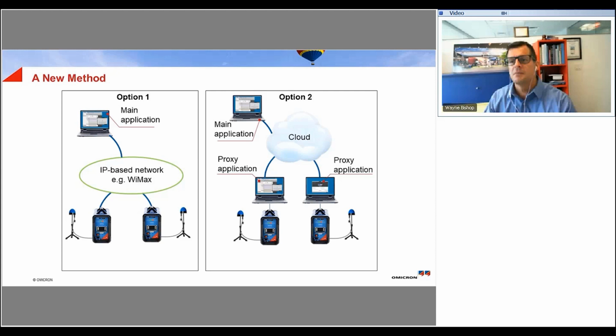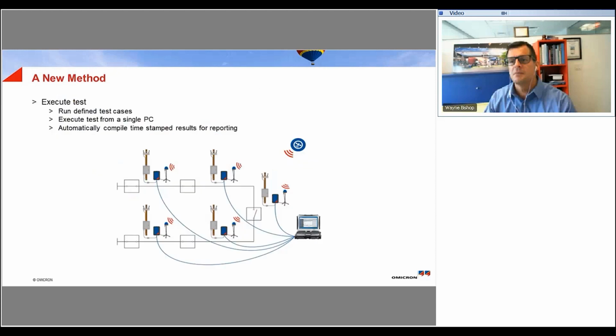So once we establish some kind of synchronization, whether it be GPS, IRIG-B, whatever it is, the test cases can then be executed. The software can then calculate the resulting fault values for each device at each location. If this test is now executed, the testing software should be able to upload all the test values into all of the test sets simultaneously via the GPS synchronization at the remote end. And once they download all the test procedures, the test sets can then all start synchronously.